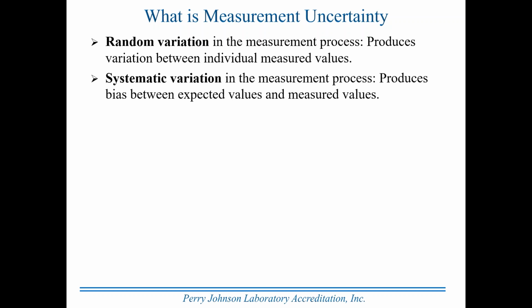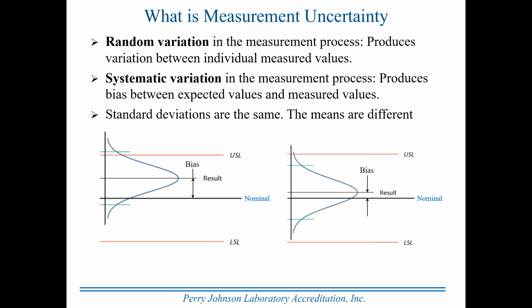Systematic variation, on the other hand, in the measurement process produces bias between an expected value and a measured value. Let's look at these two graphs. In both cases, the standard deviations are the same, so the width of the curves and the dispersion of data within the distribution is constant. The means, however, are different. You'll notice the one on the left-hand side, the bias is the difference between nominal or expected value and the actual result. A fairly large bias causes the curve to be shifted to where the green line on the top is above the red line on the top. So it exceeds the specification on the high side.